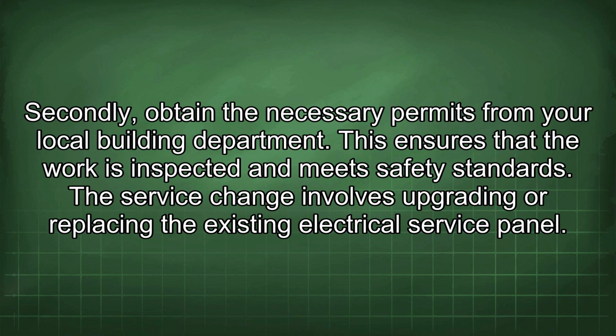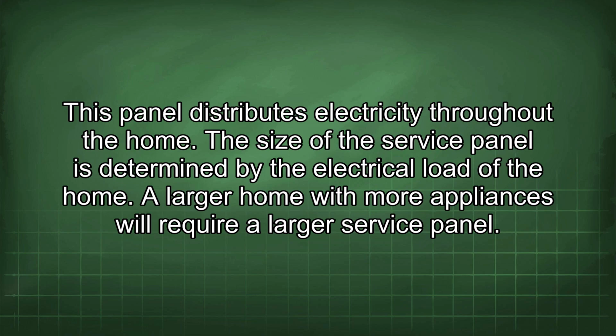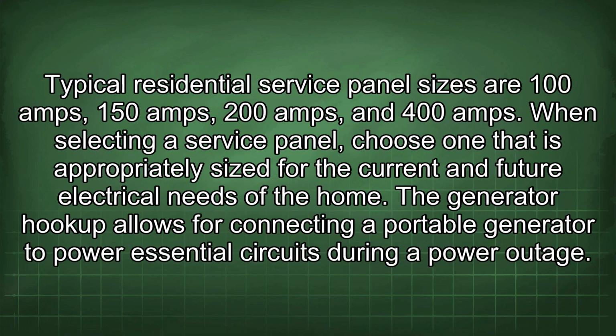The service change involves upgrading or replacing the existing electrical service panel. This panel distributes electricity throughout the home. The size of the service panel is determined by the electrical load of the home. A larger home with more appliances will require a larger service panel. Typical residential service panel sizes are 100 amps, 150 amps, 200 amps, and 400 amps.